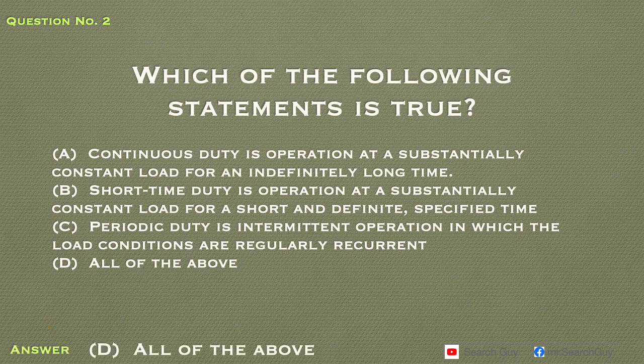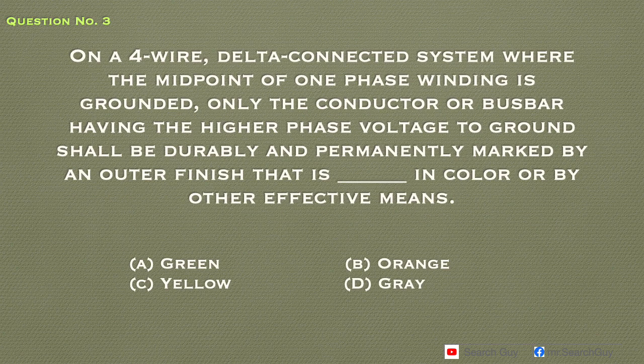Answer. D. All of the above. Question number 3. On a 4-wire, delta-connected system, where the midpoint of one phase winding is grounded, only the conductor or busbar having the higher phase voltage to ground shall be durably and permanently marked by an outer finish that is blank in color or by other effective means.